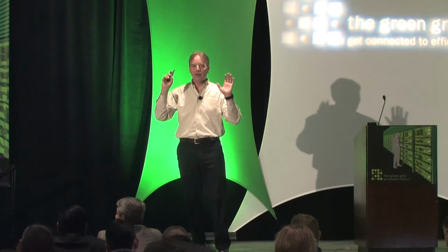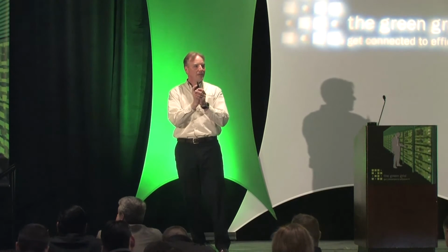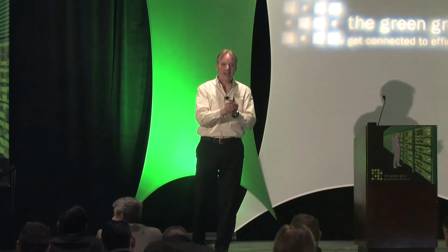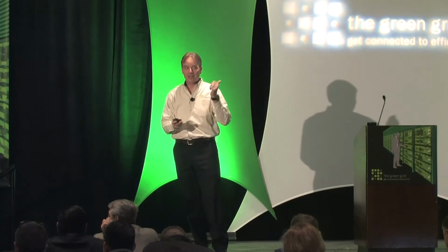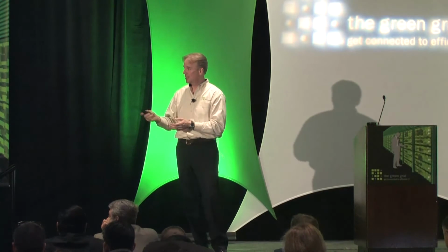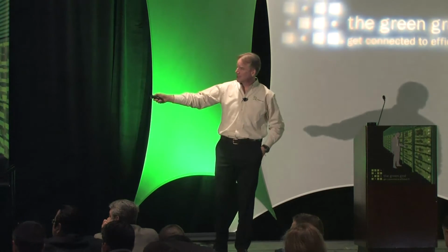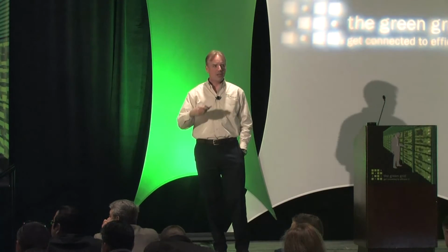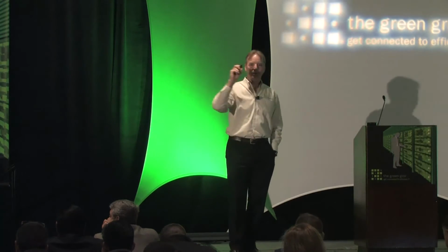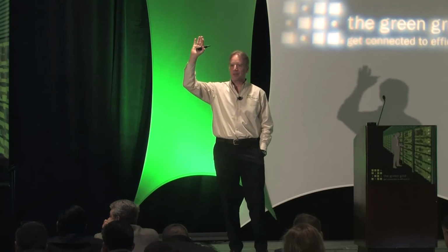They blew me away. What I was looking for was the ability to have free cooling year-round, and we got high-density packaging and outdoor components. This changed my mind on a couple things, as I talk about in the top 10. You'll see in a minute. So after this, we started looking at the overall site. So now we were in commission in January, and okay, who here has ever done level 3 PUE measurement?